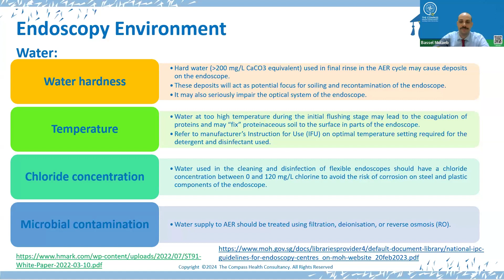Temperature of the water is important. Too high a temperature during the initial flushing stage may lead to coagulation of the proteins, causing fixation of the protein soiling on the surface of the endoscope. So you need to refer to the manufacturer instructions for use to select the optimal temperature required for the detergent and disinfectant that is used. In addition, regarding chloride concentration, water used in cleaning and disinfection of flexible endoscopes should have a chloride concentration between 0 and 120 milligrams per liter to avoid the risk of corrosion on steel and plastic components of the endoscope. And lastly, microbial contamination. The water supply coming to the endoscopy unit, especially to the AER, should be treated using filtration and should be RO water.